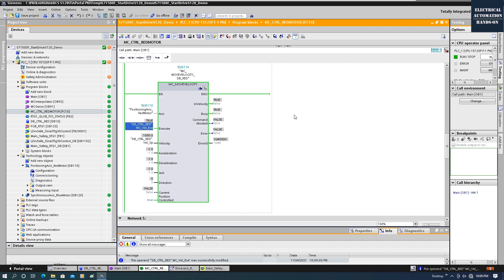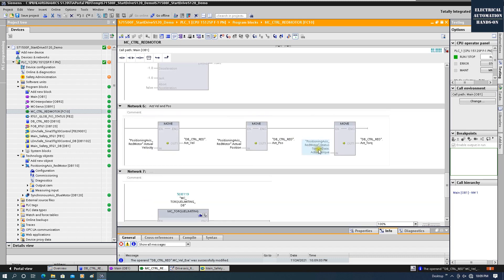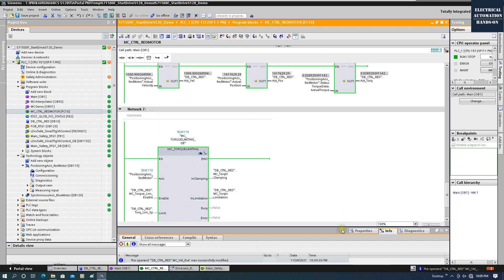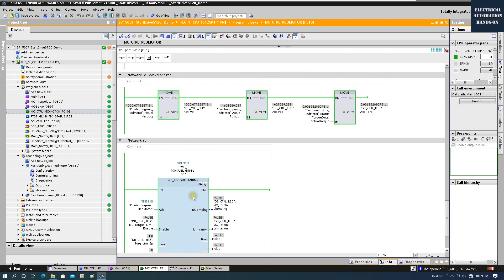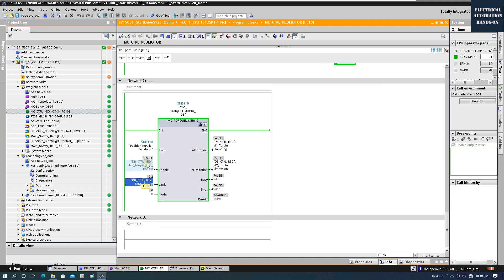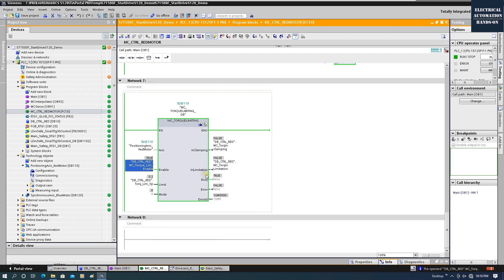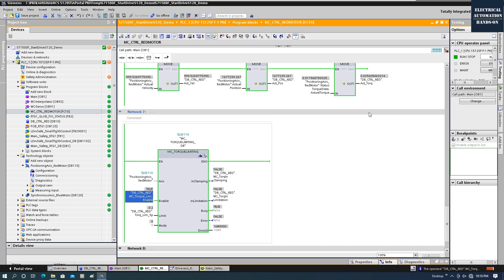Now the motor is running. We can check the actual torque value from the drive by going to TO Status > Torque Data > Actual Torque Value. We can see that with zero load, the actual torque is very low. Then we can go to MC_TorqueLimiting, prepare a limitation setpoint, enable it, and set the limitation value.